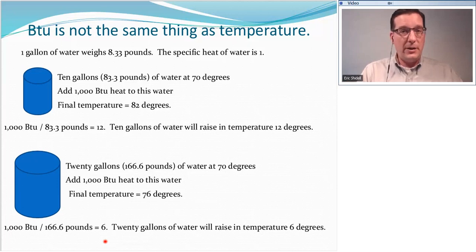We're going to experience some heating systems that operate on very low water temperatures, but heat an entire home or building or garage very, very well in very cold weather. On the other hand, we're going to see other hydronic systems that use very high water temperatures. It all depends on the way that system is designed and the way that it is meant to function, and that relates to what type of boiler do we have, what type of distribution system do we have, what type of emitters do we have, before we can analyze whether or not our water temperatures are appropriate.